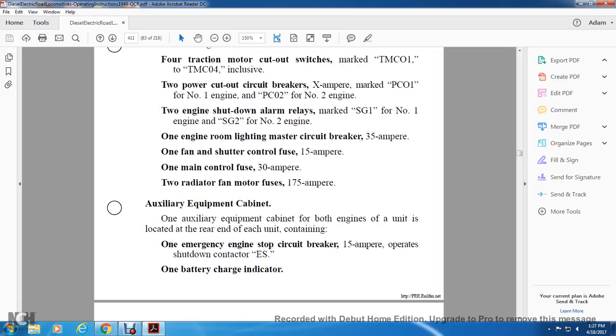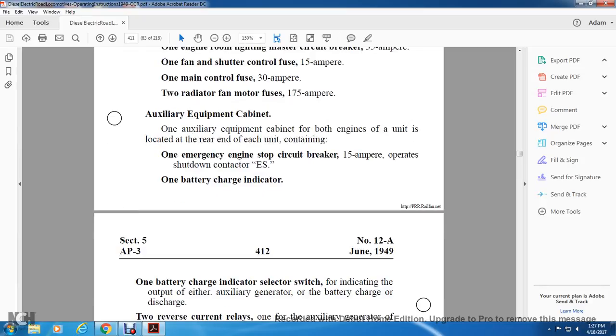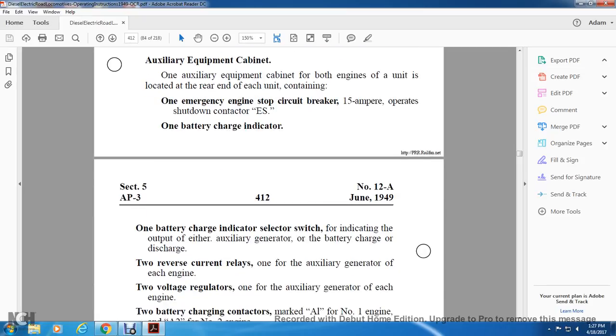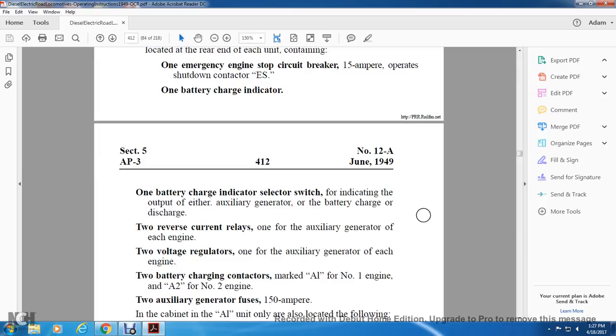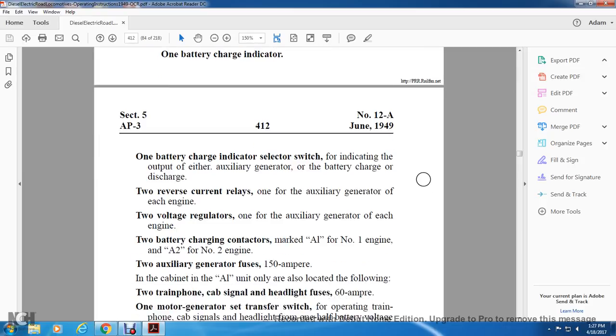Auxiliary equipment cabinet. One auxiliary equipment cabinet is located at the rear end of each unit, containing one emergency circuit breaker, a 15 ampere operating shutdown contact ES, and one battery charge indicator with a selector switch for indicating the output of the auxiliary generator for battery charge or discharge. It also contains two reverse current relays, one for the auxiliary generator of each engine, two voltage regulators, one for the auxiliary generator of each engine, two battery charge contactors marked A1 for the number 1 engine and A2 for the number 2 engine, and two 150 ampere auxiliary generator fuses in the cabinet.